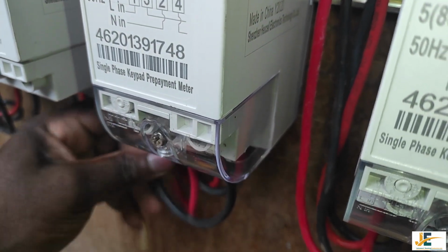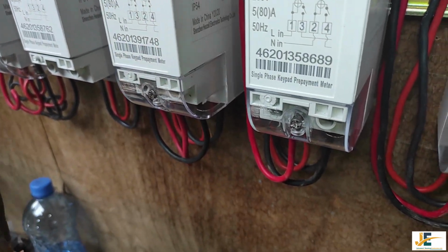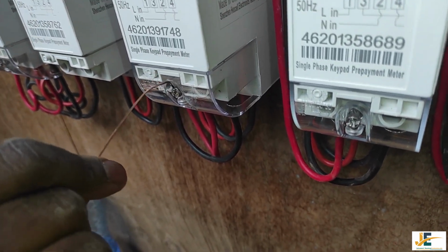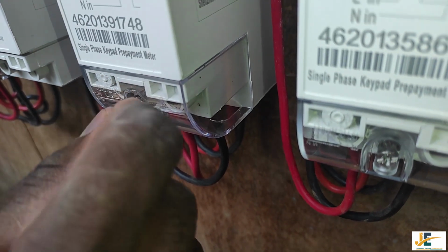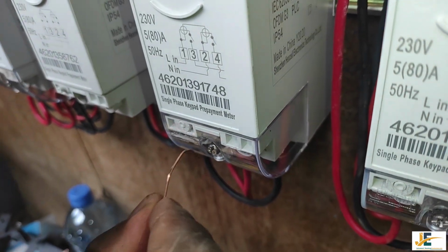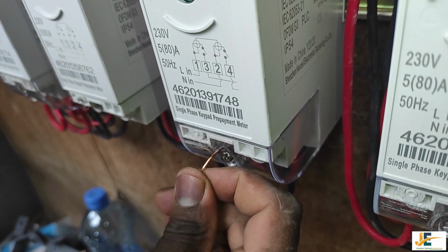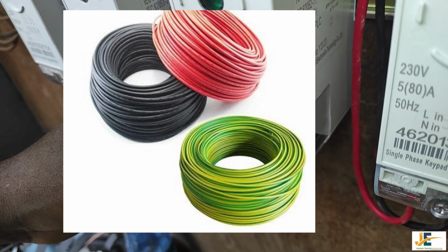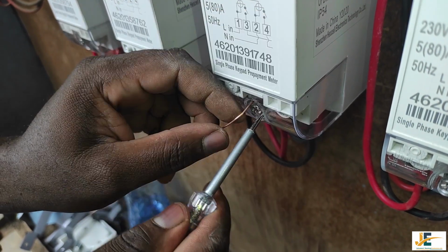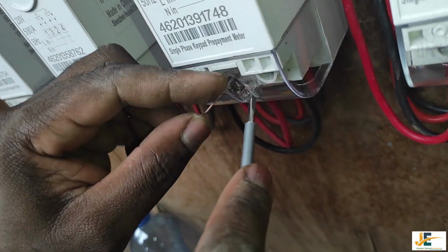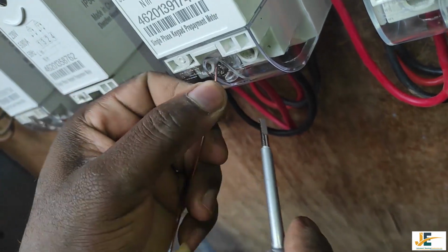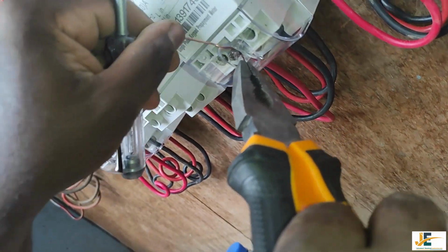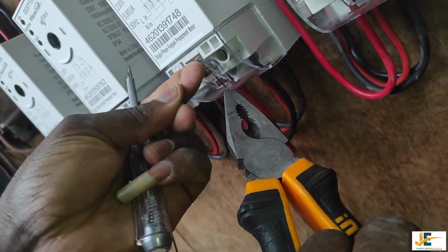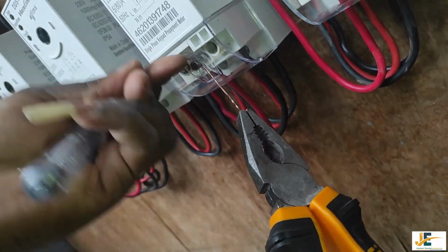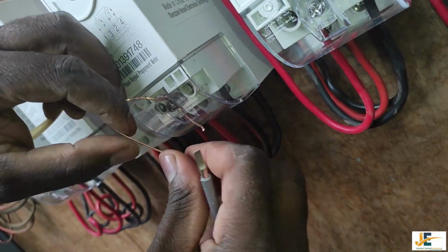So as for me, because now clamping these cables which are 2.5 millimeter, it can be more work. I would advise someone to use 6.0 millimeter, depending on the load of the house. But in this case, talking of single rooms, whereby maybe you have a socket and one point of lighting, or maybe just a point of lighting, you can use the right size of cable, and then you make a joint where the right size of cable and the 2.5 millimeter cable meet, and then by doing so you'll be on the safe side.